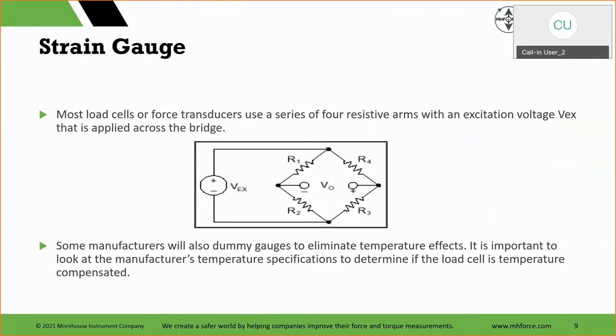There are different meters, battery powered versus DC versus AC. There's a difference in output. So interchanging meters is something that we try to elaborate on in our classes, to say don't do it. There's a lot more that needs to be done, and measurement traceability, or metrological traceability, needs to be established. So we're gauging a load cell, and when gauging, you also use some dummy gauges and things to eliminate temperature effects.